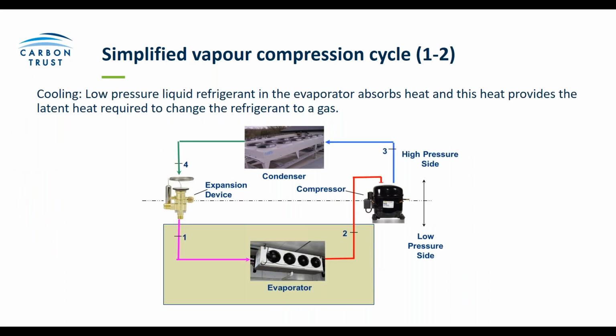So the first stage of a standard refrigeration system is the evaporator. So this will start somewhere in your cold room, your fridge or your freezer, and it's where the low pressure liquid refrigerant will absorb heat and essentially evaporate into a gas. So efficiency gains can be found here when it's made easier for that liquid to collect that heat and be evaporated. So the thing to consider during this cycle is that pressure and temperature are proportional. So the pressure is how the refrigerant is moved around the system and essentially how the heat is transferred.